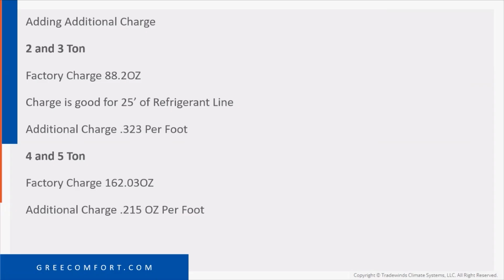Additional charge information. I just wanted to clarify this. This is in the owner's manual / installation instructions, but I was kind of looking through this myself. So the 2 and 3 ton has the factory charge of 88.2 ounces. Well, the unit is smaller, obviously, than the 4 and 5 ton, so it's not going to hold as much refrigerant. But I think that also is playing a role in our total charge. So this says your charge is good for 25 feet of refrigerant line. Additional charge after the 25 feet, you're going to use 0.323 ounces per foot. I'm sorry I didn't put ounces per foot, but it's ounces per foot.